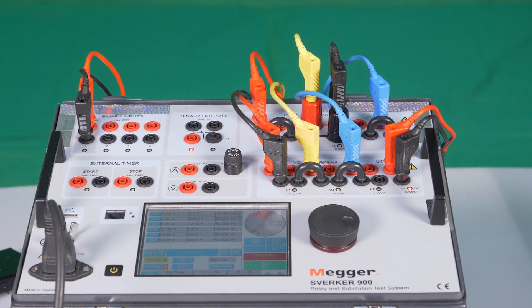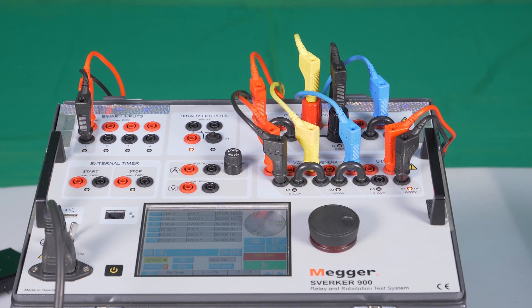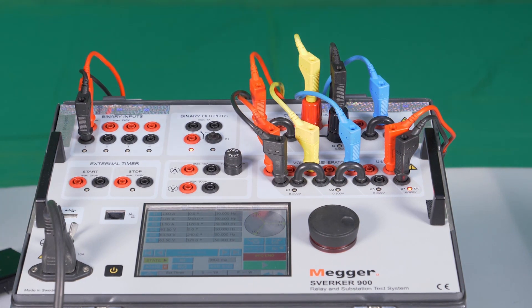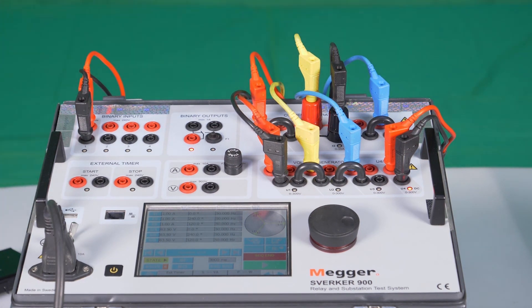State 1 is configured as a healthy state with 63.5 volts for a period of 3 seconds. State 2 is configured for overvoltage condition with 90 volts.